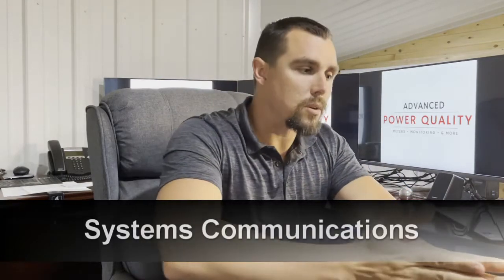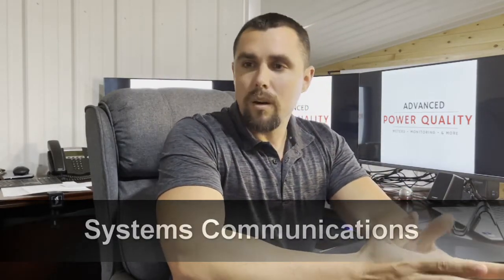The next item, while we're on voltage — I want to talk about voltage levels. Utilities have all sorts of voltage-controlling devices: LTCs, load tap changers at the substation, capacitor banks, regulator banks, and reclosers that sense voltage and communicate. They have SCADA systems that provide this data, and all these systems interact accordingly to regulate voltage levels on the system.